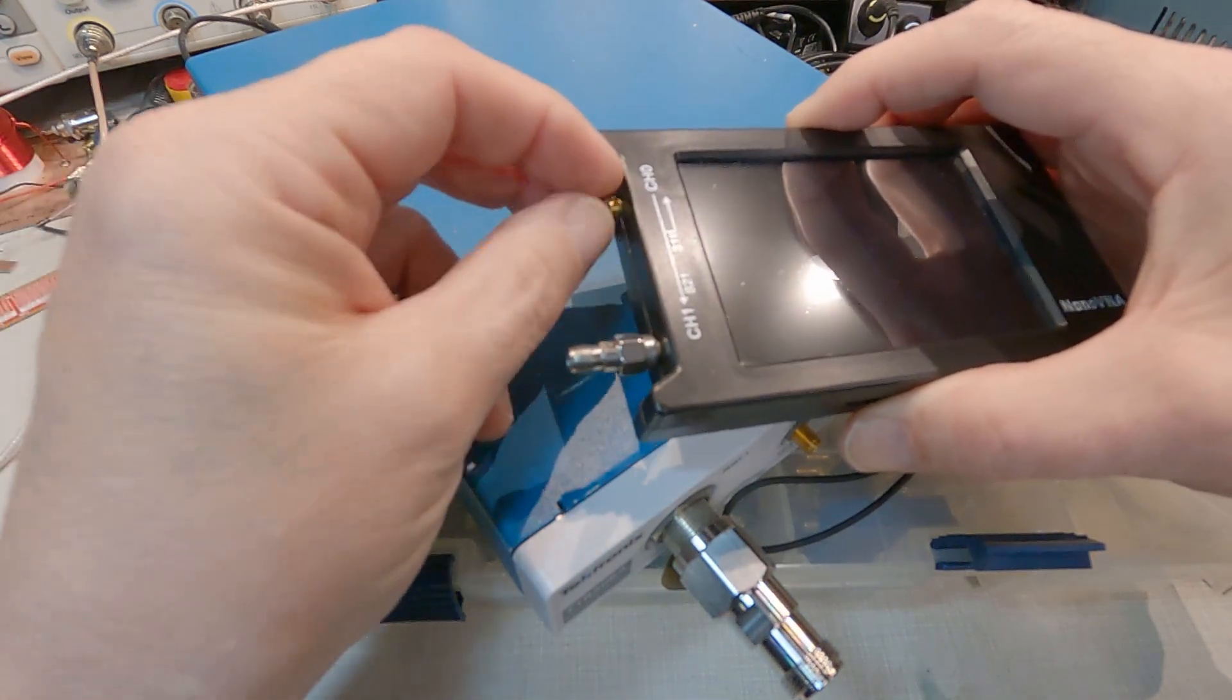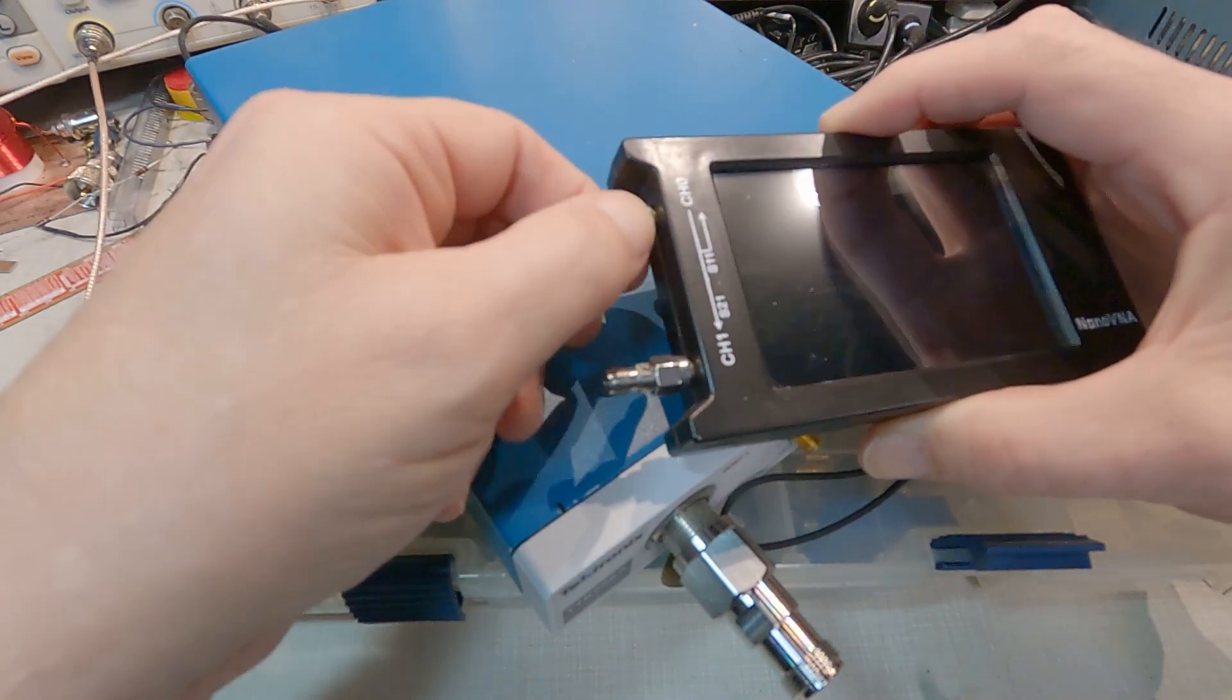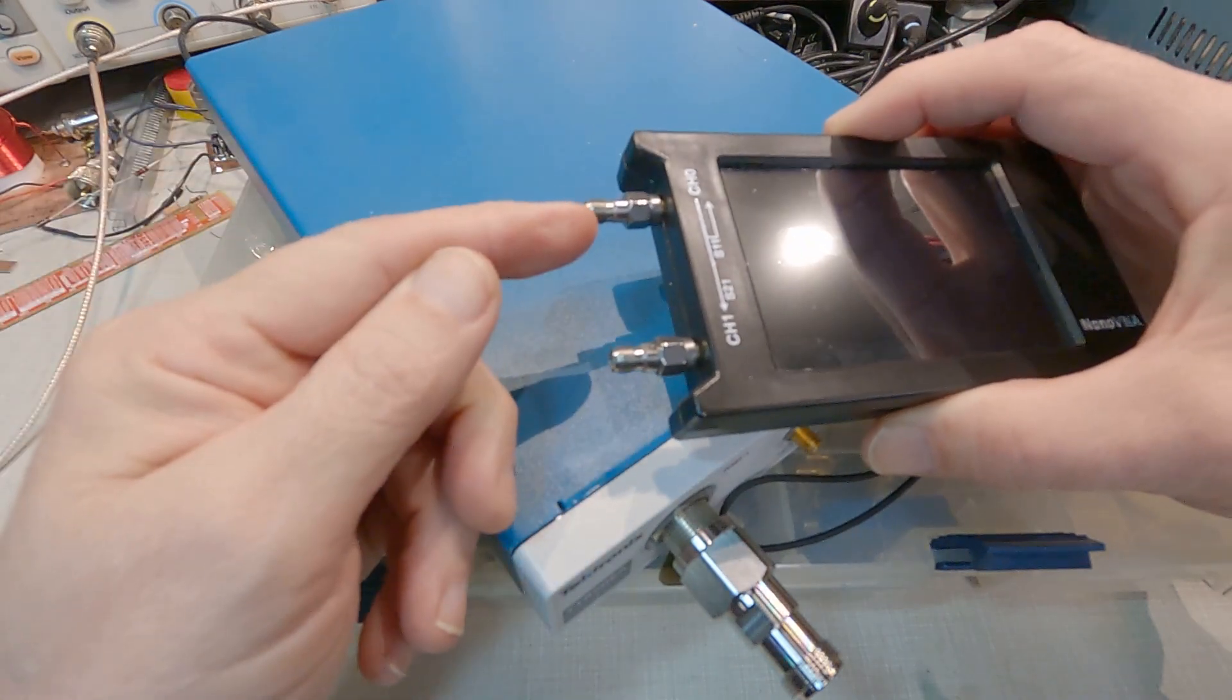So I'll put a decent connector saver on there and leave that on there and do all of my calibrations, all my measurements, all my connections to the end of the connector saver here.